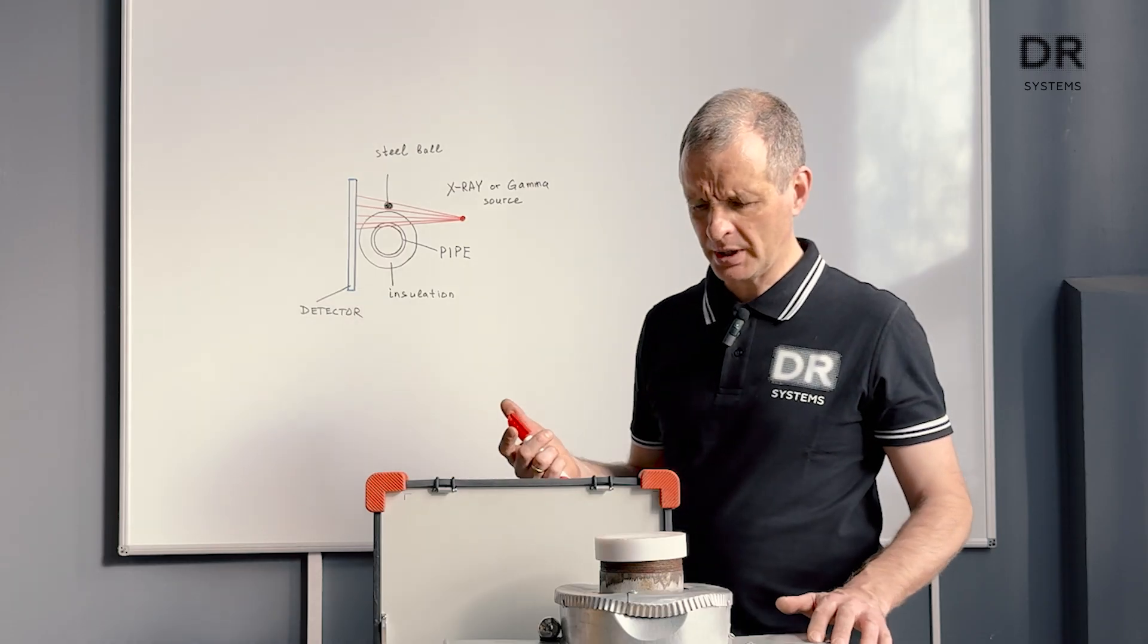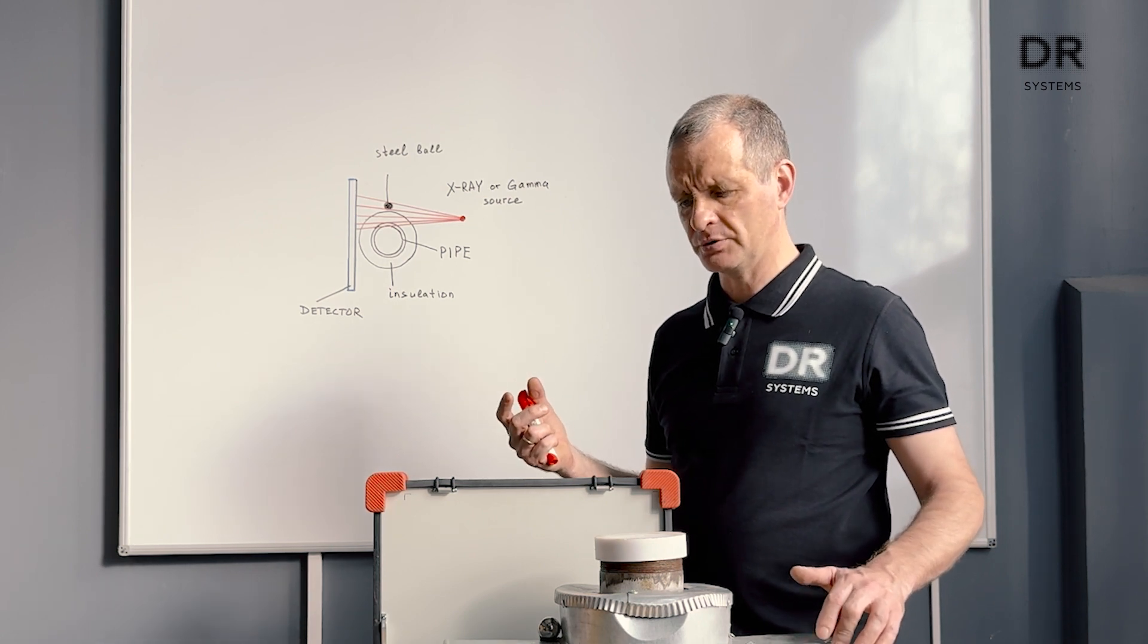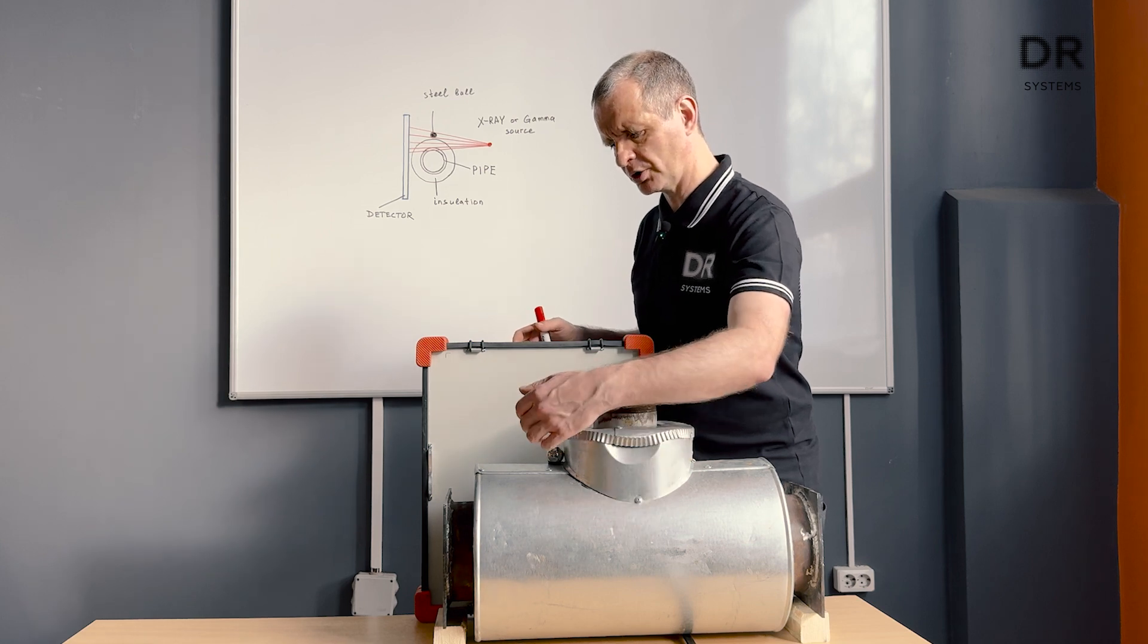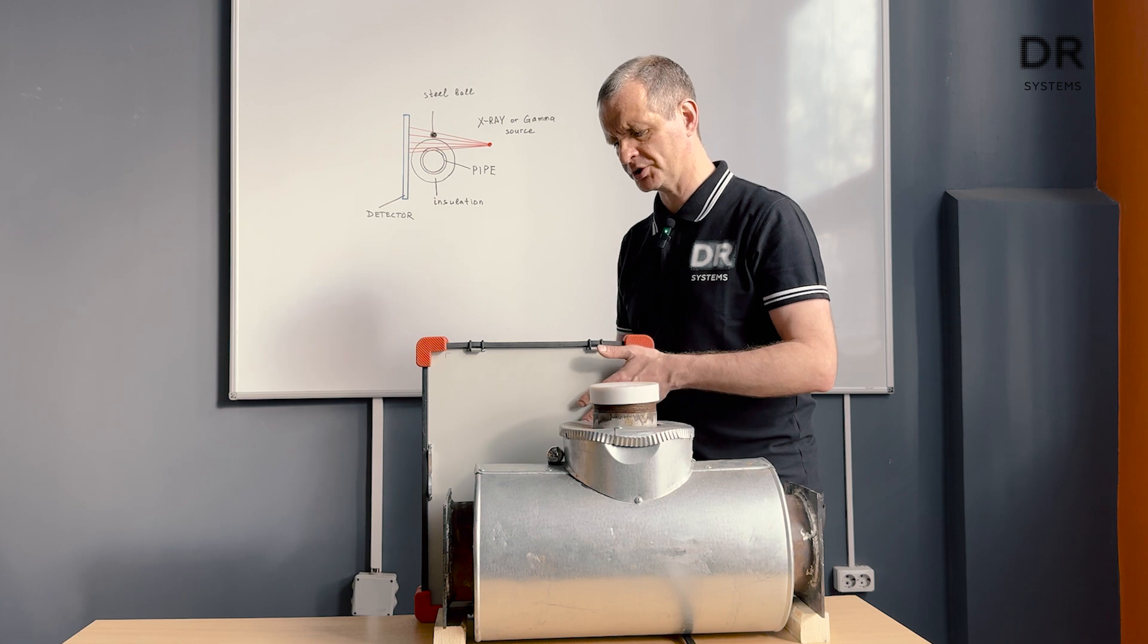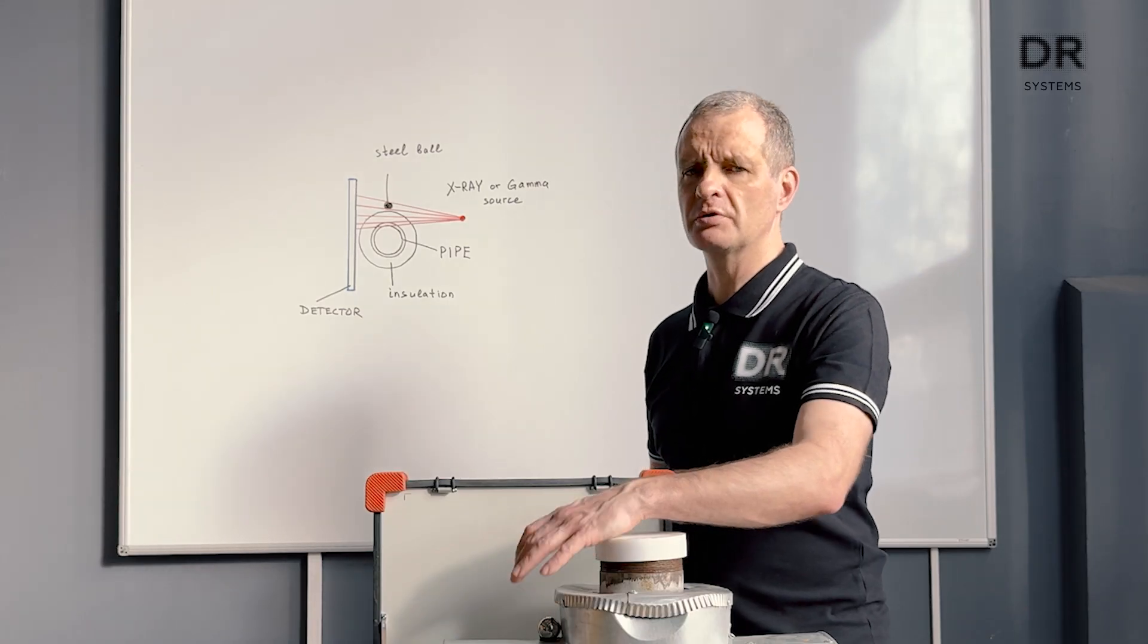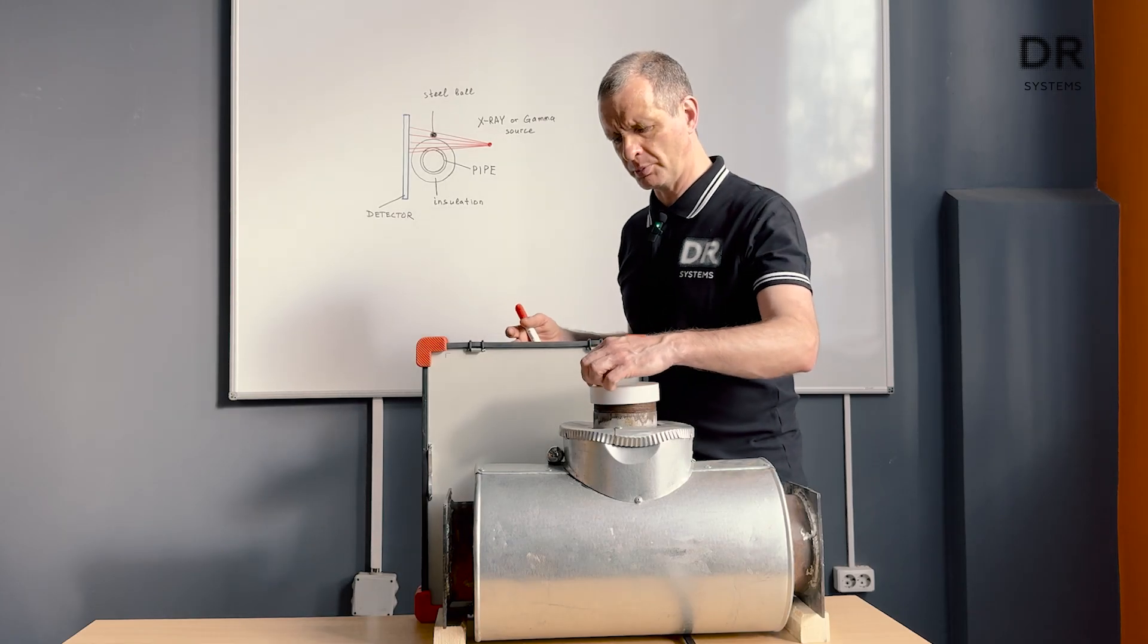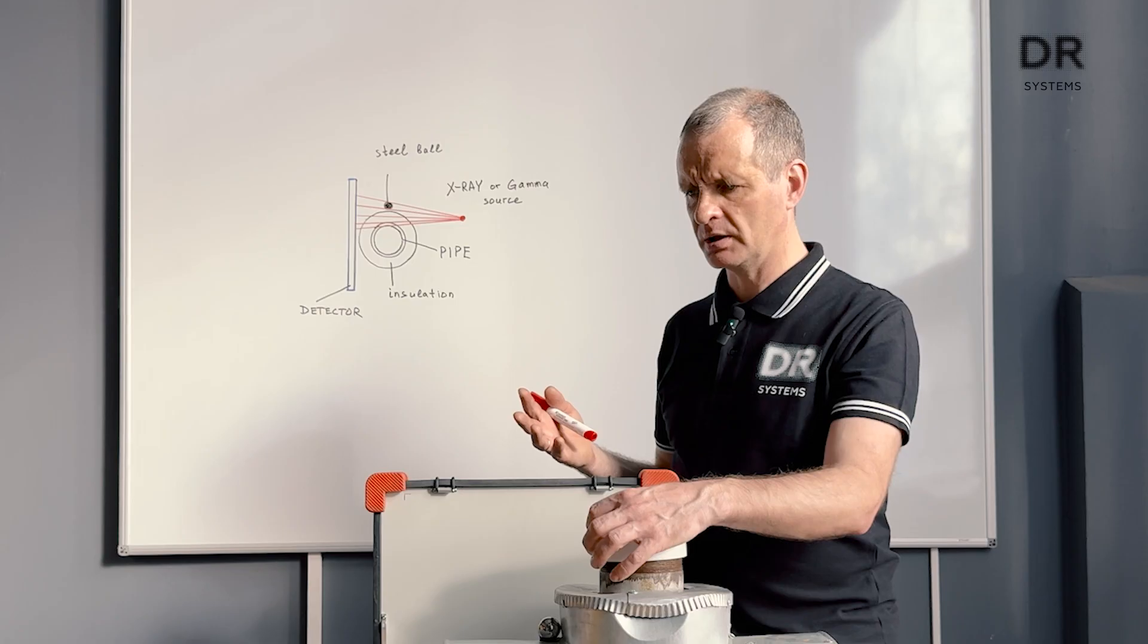To measure the pipe wall thickness you just have to take an image like this. Here is an x-ray source, here is your ball, here is your pipe wall and you will see the projection of all these parts on the detector. The ball will be used for size calibration and you will simply see the pipe wall on the image and you will be able to measure it directly.